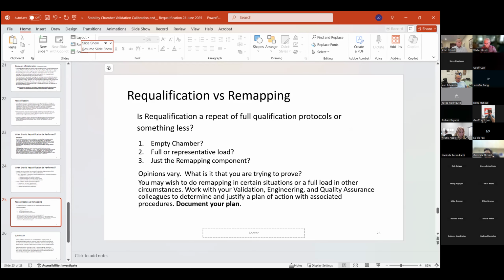Full or representative load, yes, you would want to do it with that. And just a remapping of the component itself, you could do that too, depending on what the nature of the problems might be in the chamber. So if it's just simply a little disturbance in the air, that's one thing. If it's a major change in the mechanics or performance, then you would want to go further. Opinions vary. What is it that you're trying to prove? You may wish to do remapping in certain situations or a full load in other circumstances. Work with your validation, engineering, and quality assurance colleagues to determine and justify a plan of action that's associated with your procedures, and then document your plan.